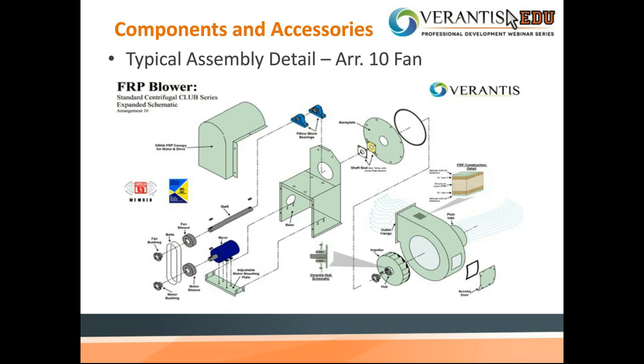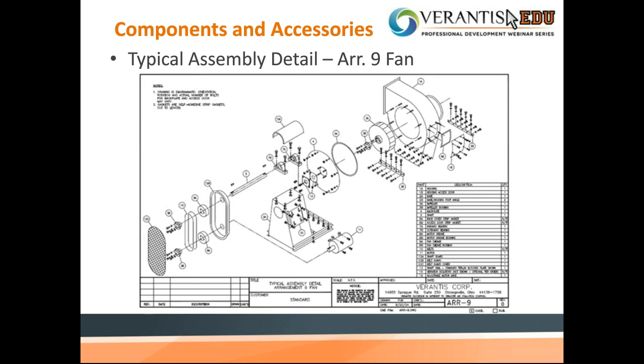The next slide is an arrangement 9 style fan. It's basically all the same components except for where the motor is located. The motor in this case is located on the side, and it sits on top of an adjustable base. Like I said, that's what keeps the tension on the belts. Instead of having a canopy in this type of arrangement, we have individual belt and shaft guards, which are all mandatory by OSHA and are typically painted bright yellow. The belt guard has expanded metal around it, so we can't reach inside of it without turning off the equipment.